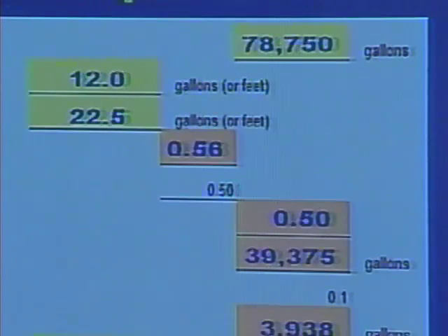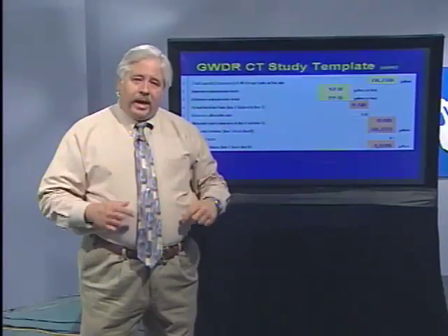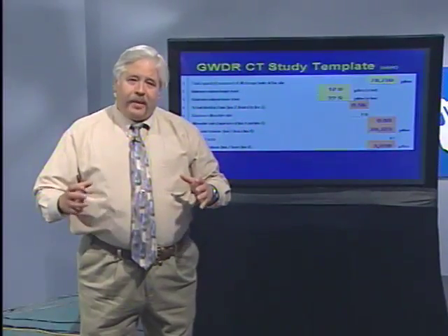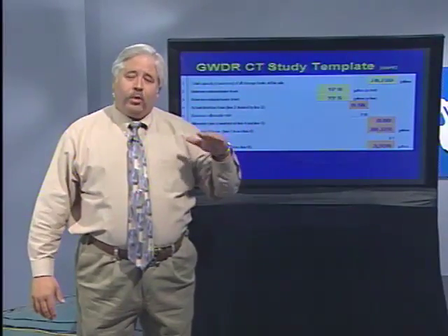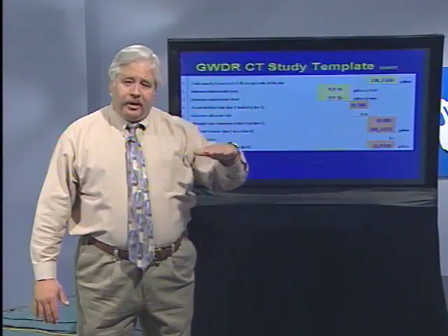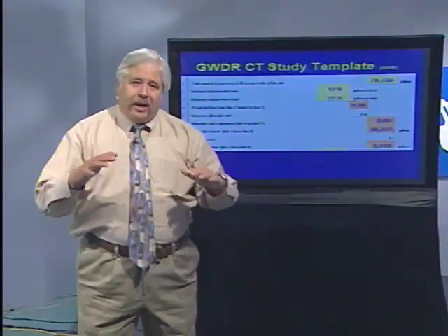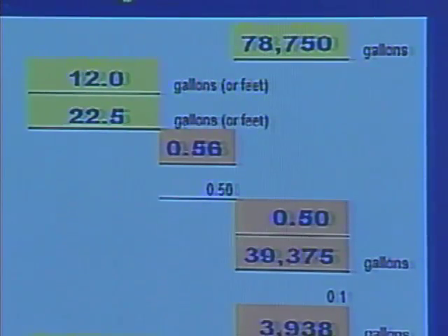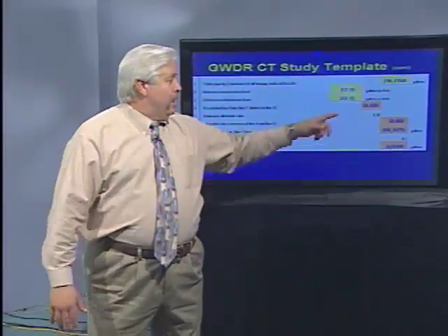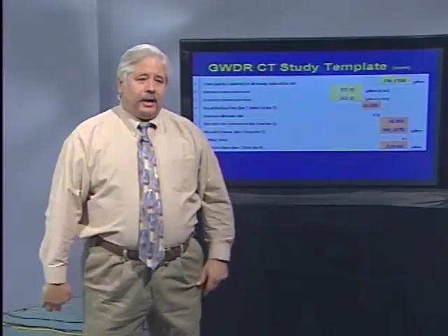When the water level in the tank drops to 16 feet, the well pump will kick on. But during periods of peak demand, the service pumps are pumping out of that tank faster than the rate at which water fills the tank. So the water level continues to drop. When everything kind of balances out, input and output, the water level in that tank gets to about 12 feet deep from the floor to the water level. At that point, with peak hours over, the output of the service pumps declines, they run less frequently, and so the water level in the storage tank starts to rise, okay?